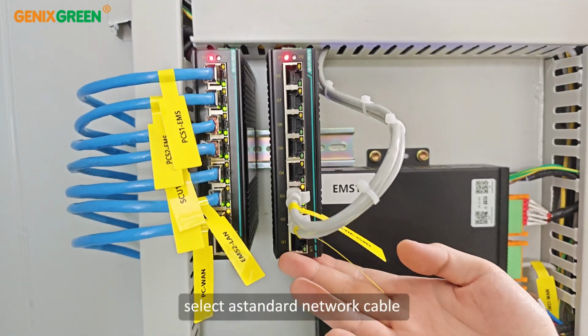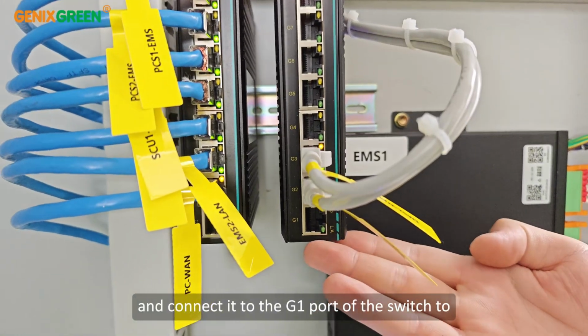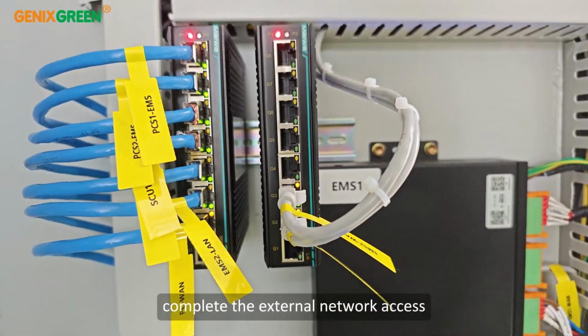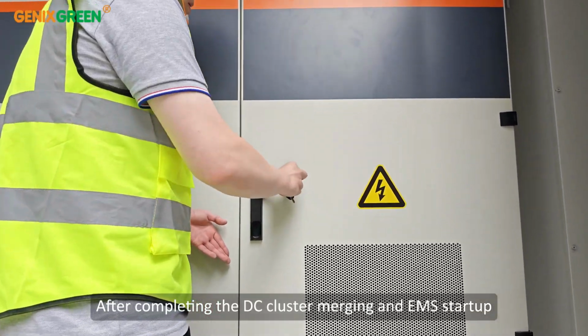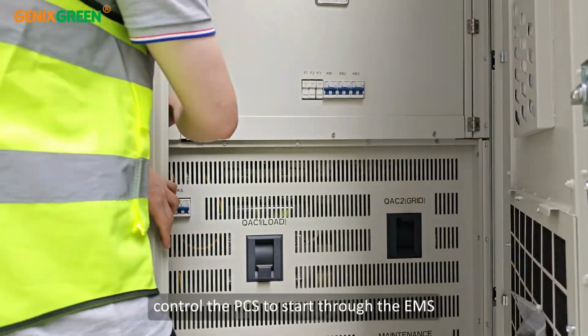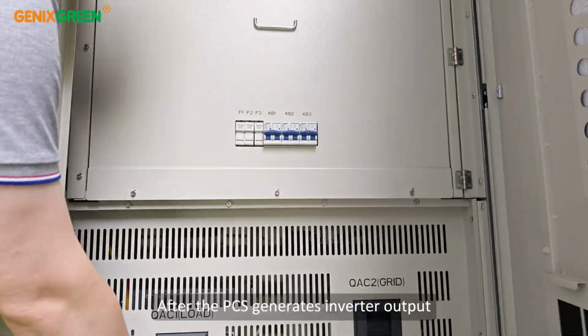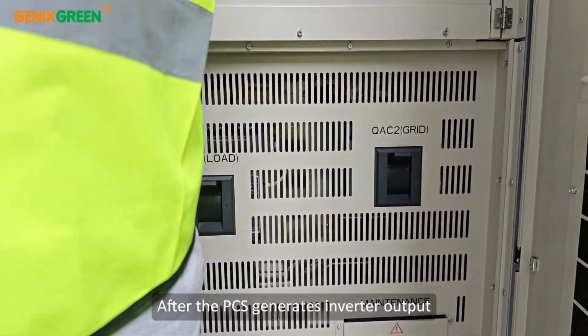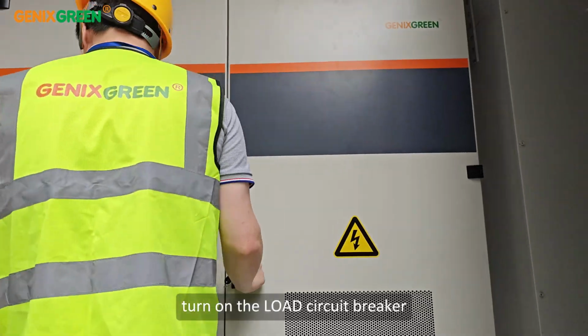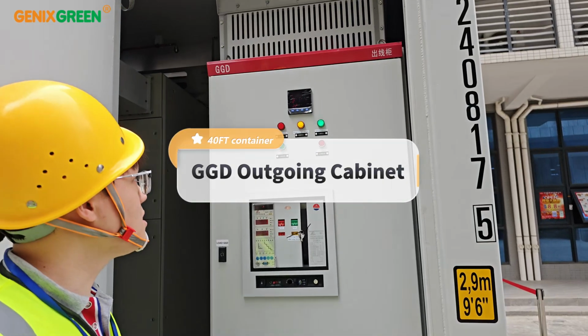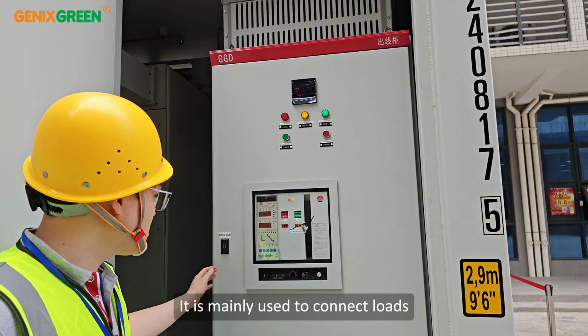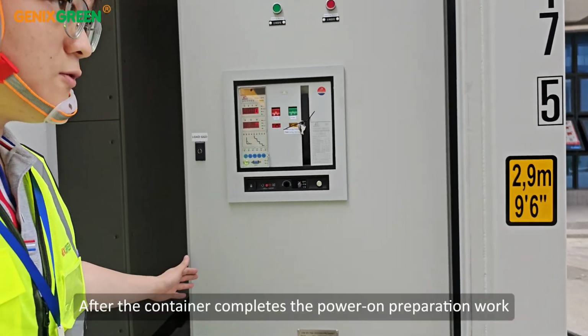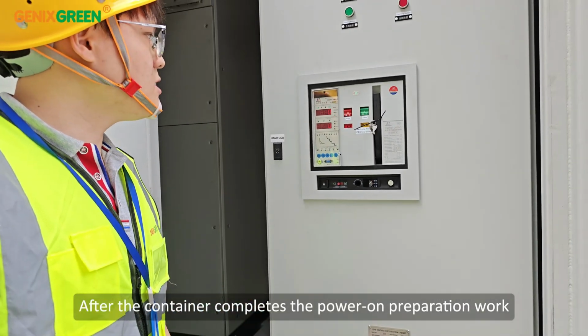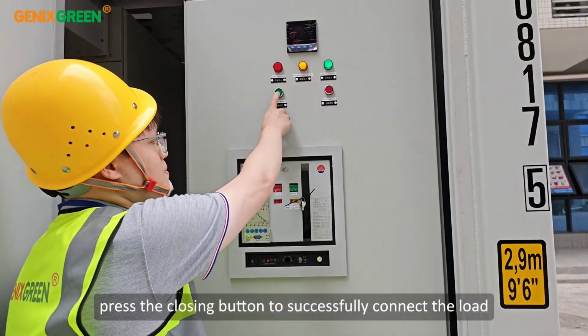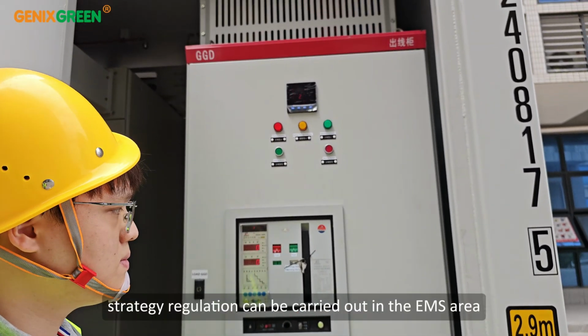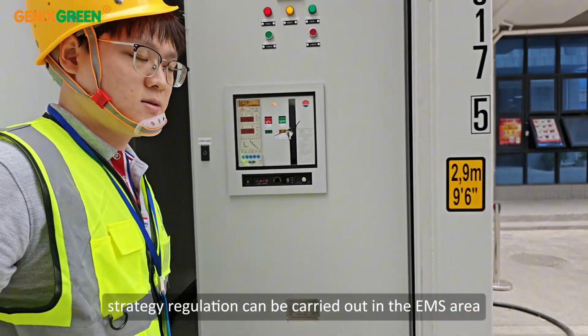During installation, select a standard network cable and connect it to the G1 port of the switch to complete the external network access. After completing the DC cluster merging and EMS startup, control the PCS to start through the EMS. After the PCS generates inverter output, use the provided accessories to turn on the load circuit breaker. It is mainly used to connect loads. After the container completes the power on preparation work, press the closing button to successfully connect the load. At the same time, strategy regulation can be carried out in the EMS area.